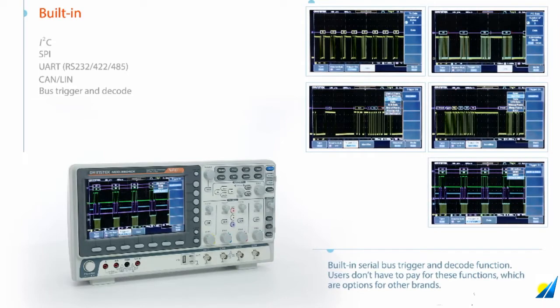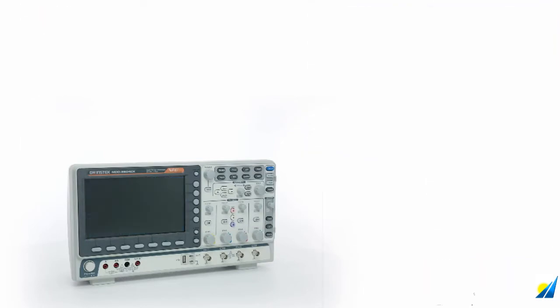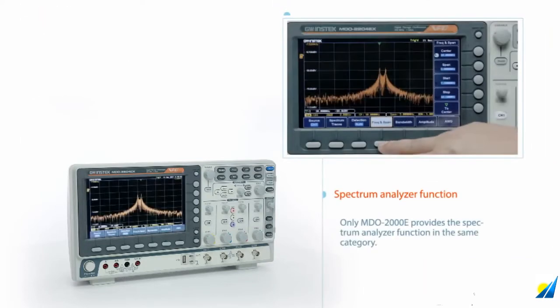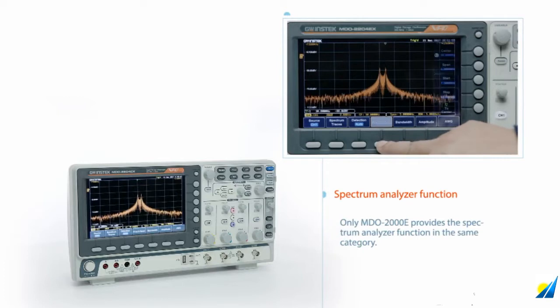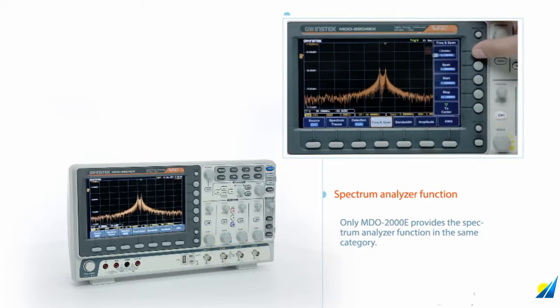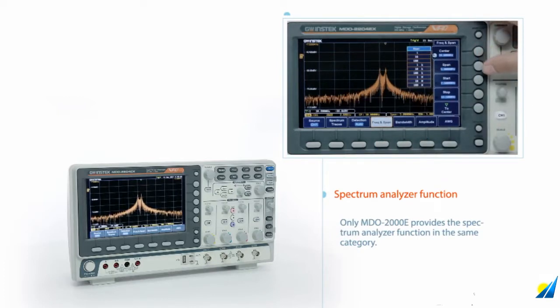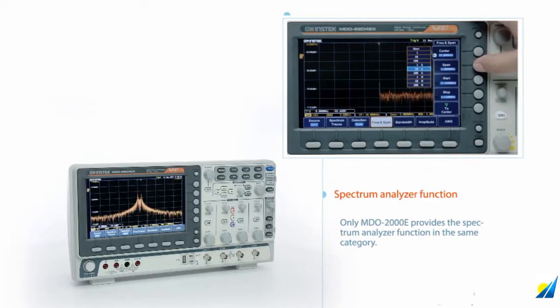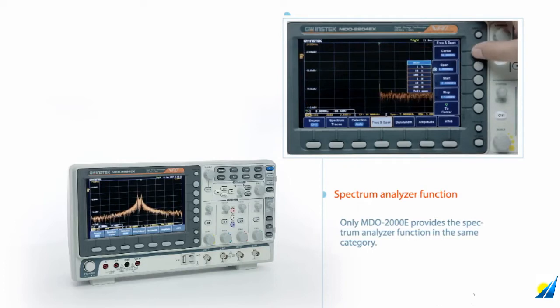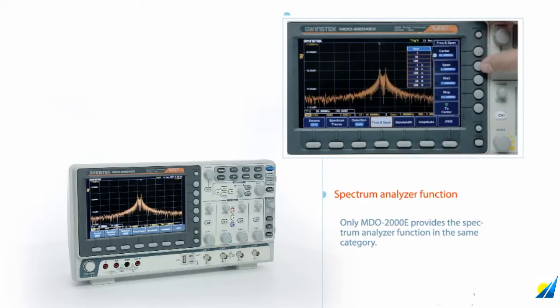Only the MDO-2000E provides the spectrum analyzer function in the same category. It allows users to set center, start, stop frequency, and span. The operation is very close to a desktop spectrum analyzer.